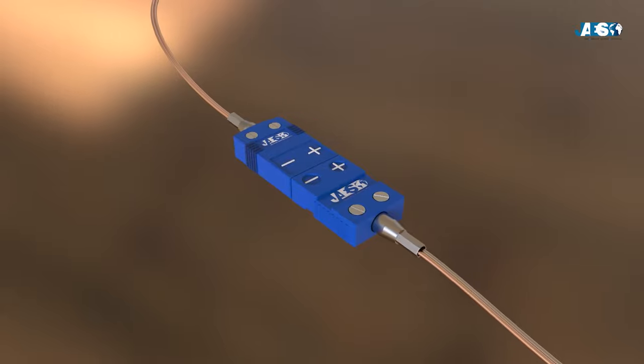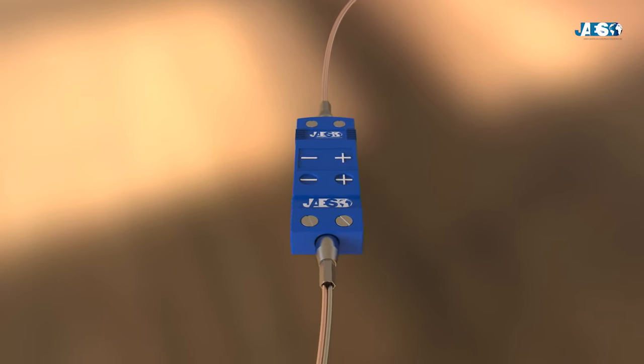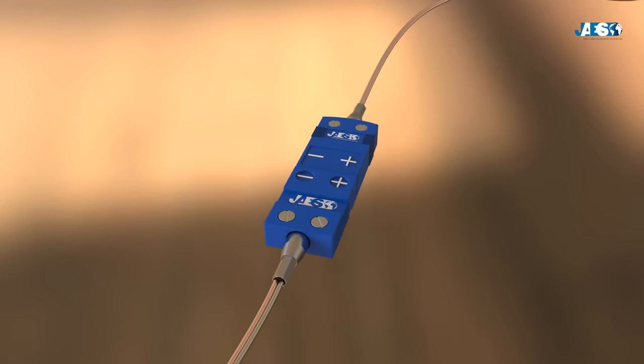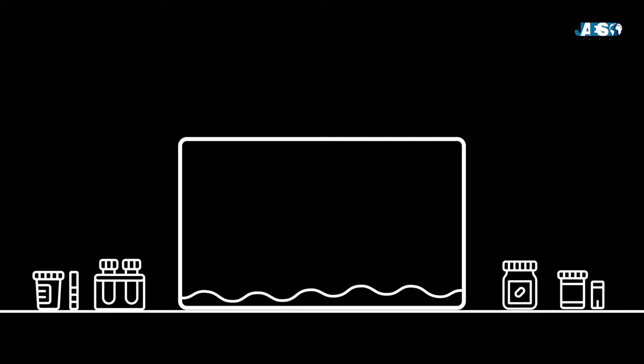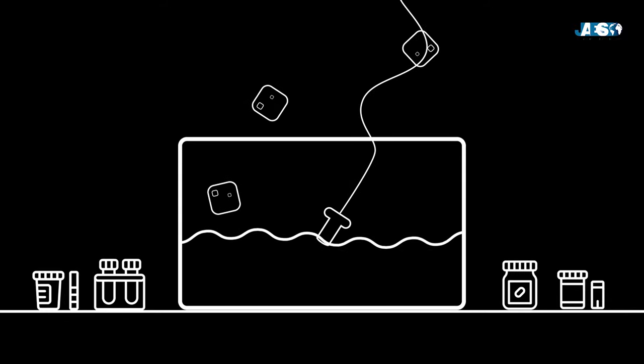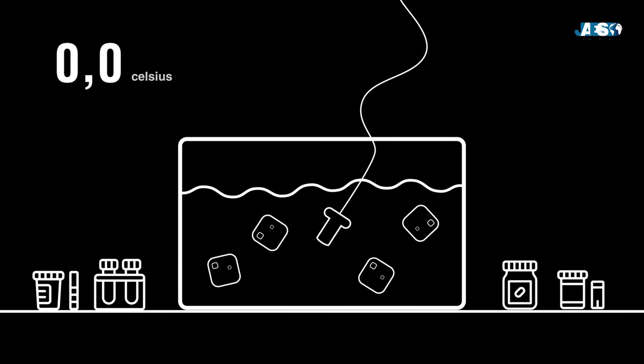For the measurement to be accurate, the cold junction must be in an environment with a known temperature to compare it to that of the hot junction. Ideally, in the laboratory, the cold junction was immersed inside a liquid solution of water and ice, therefore at a constant temperature of zero Celsius.